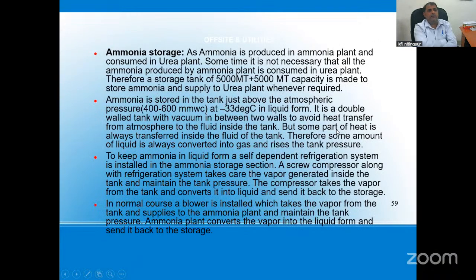Ammonia storage. Ammonia storage is the tank which stores the ammonia inside it. Our plant also produces excess ammonia. If we require 1900 ton ammonia for the production of urea, and we produce 2000 metric ton of ammonia, then this excess 100 metric ton ammonia is stored in the ammonia storage tank.